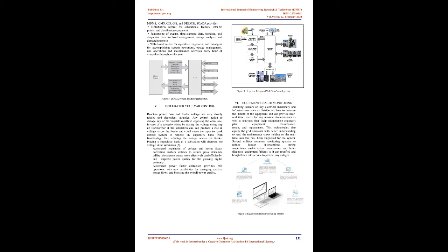Precise fault location enables the operators to send the maintenance workforce to the right, precise location and notify customers of the status of the power outage, which reduces maintenance costs, reduces the burden on customers, and helps in maintaining consumer satisfaction. 1. In Figure 3a, when a fault occurs, the FLISR system locates the fault. In Figure 3b, 3c, once the fault is located, the system isolates the feeder on both sides of the fault from both ends. The feeder is re-energized and that portion of the feeder with the fault cleared now supplies power to all customers served by those feeder sections from another.